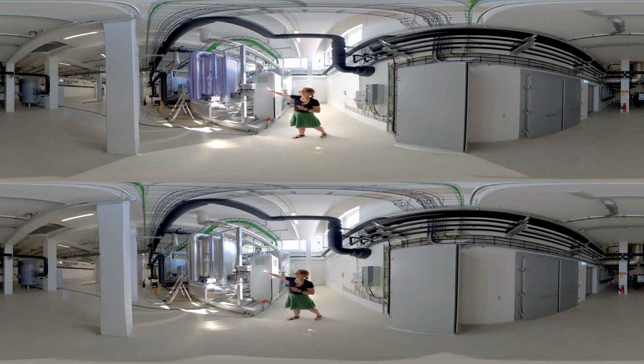The first big tank here is the evaporator, where we have the seawater coming in. At a very, very low pressure, it will boil. The steam will then be let on through a pump over here to the condenser. In the condenser, it will condense against cold water. So the refrigerant is just water here. We don't want any risk of contamination into the seawater, because that we want to put out into the harbor again after we oxygenize it.